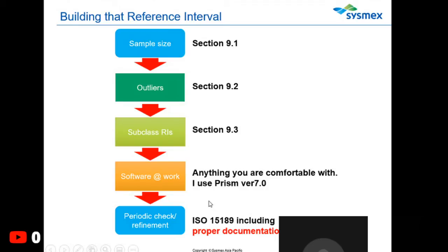It is important because of ISO 15189 for the laboratory. If the laboratory is participating to get ISO certification, it also gives you a very detailed list of what you need to prepare for reference interval documentation. And CLSI EP28 is sufficient, I would say, if you are able to follow all the section guidelines to build that documentation for ISO 15189.